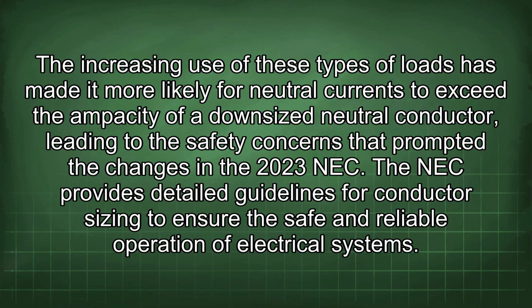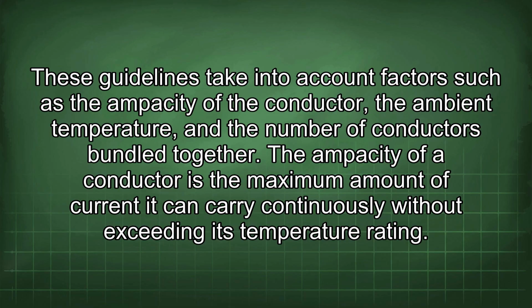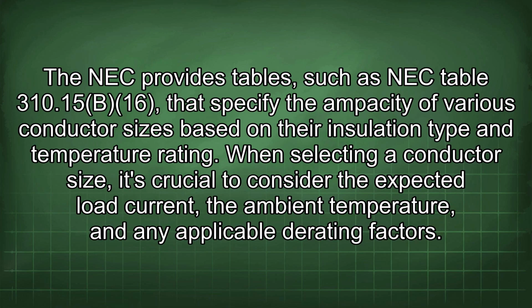The NEC provides detailed guidelines for conductor sizing to ensure the safe and reliable operation of electrical systems. These guidelines take into account factors such as the ampacity of the conductor, the ambient temperature, and the number of conductors bundled together. The ampacity of a conductor is the maximum amount of current it can carry continuously without exceeding its temperature rating. The NEC provides tables such as NEC Table 310.15(B)(16) that specify the ampacity of various conductor sizes based on their insulation type and temperature rating.